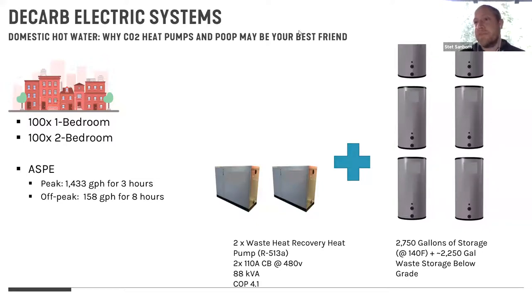The Vancouver Olympic Village is entirely heated and cooled with a sewage heat exchange heat pump system, the entire Olympic Village, and has been since the Vancouver Olympics. So that system's been running. One of the companies has a small unit for multifamily domestic hot water, and then the large one, which is what we used at DC Water. And that's actually going into the new enormous Amazon campus in Virginia. Both of the companies that I know of and have worked with have systems that scale at the urban scale and the building scale. The technology differs between the two based on the flow rates, because for these big urban scale projects, the flow rates are just kind of bonkers.